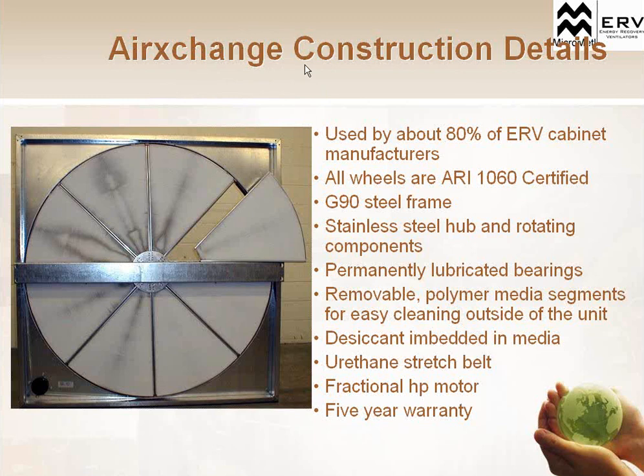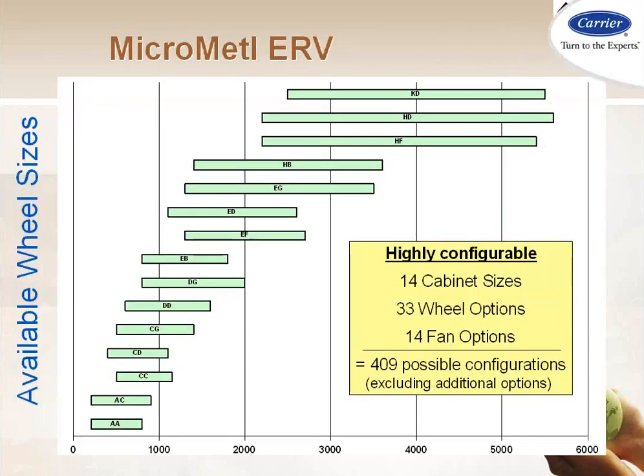Airxchange is a manufacturer of energy recovery wheels that's used predominantly in most applications. Most manufacturers that are using ERV, Airxchange is a very common manufacturer of that wheel. Specifically, MicroMetl is one of the companies that Carrier works with and TEC works with. MicroMetl manufactures their own cabinet and then uses the Airxchange wheel in their cabinet. So each one of their cabinets will have a rating with that Airxchange wheel. And then when you mate that up with another piece of equipment, then you'll get another rating. We'll talk about that as well.